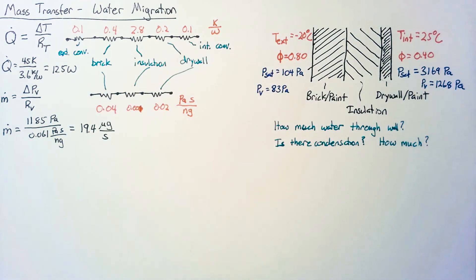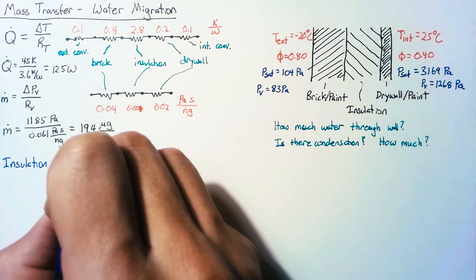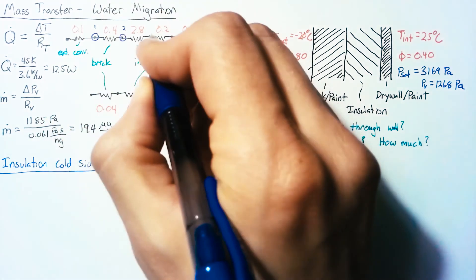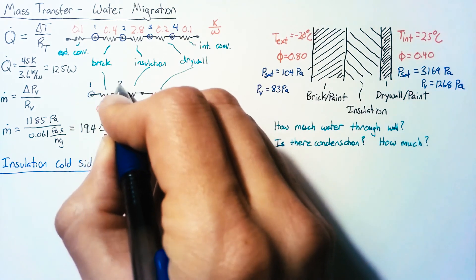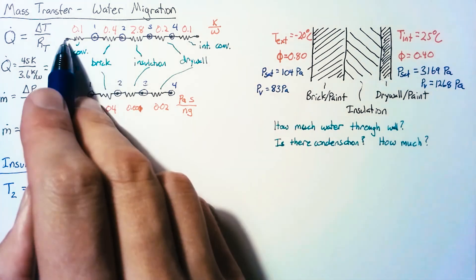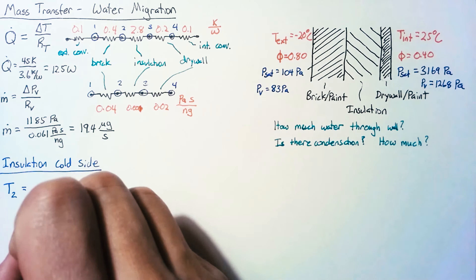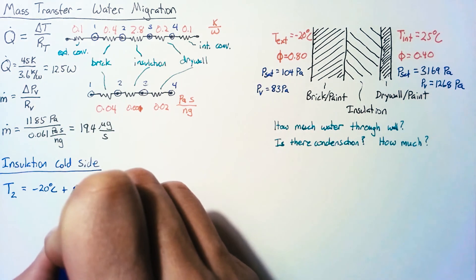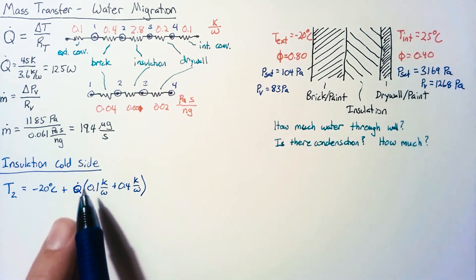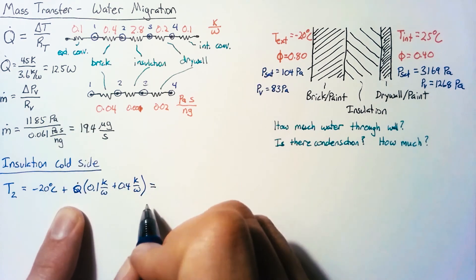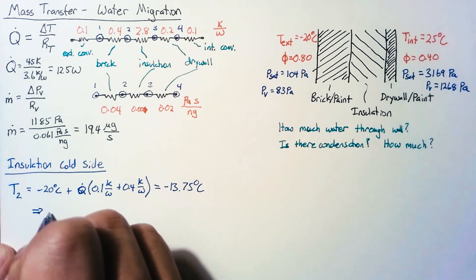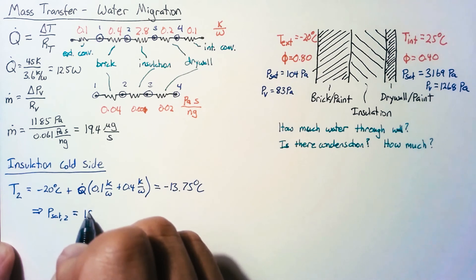The critical location is the cold side of the insulation, where the saturation pressure is lowest. We label each node for clarity. The temperature at node 2 — the cold side of the insulation — is calculated starting from the outside temperature of negative 20°C and adding Q-dot multiplied by the resistances passed through. With Q-dot of 12.5 W, we get a temperature of negative 13.75°C. Looking up the saturation pressure at this temperature gives us 187 Pa.